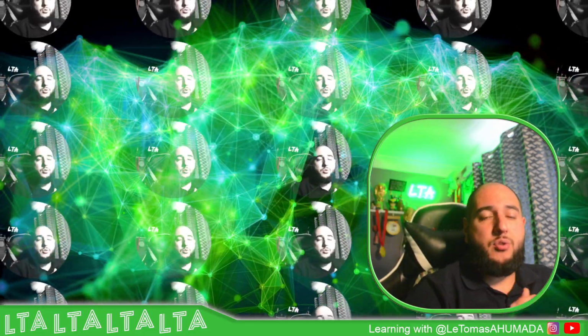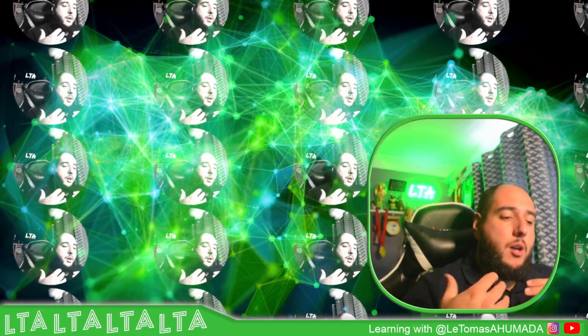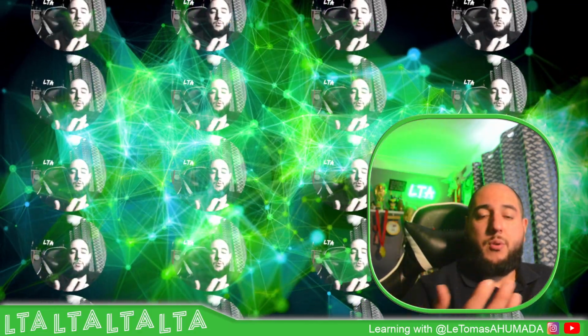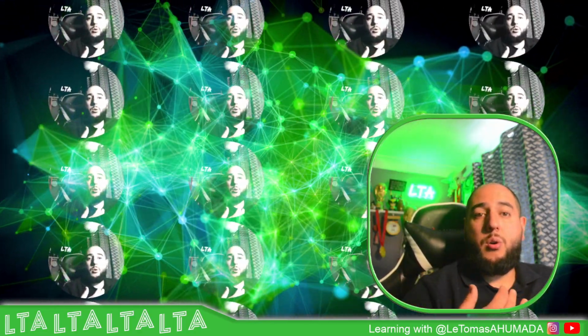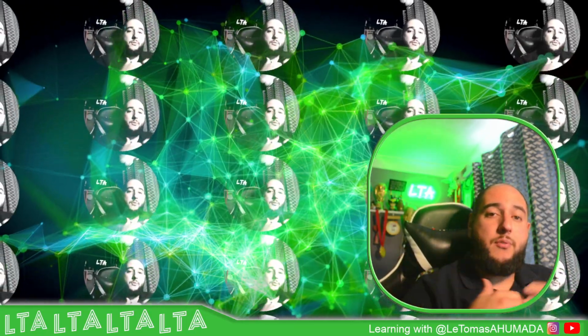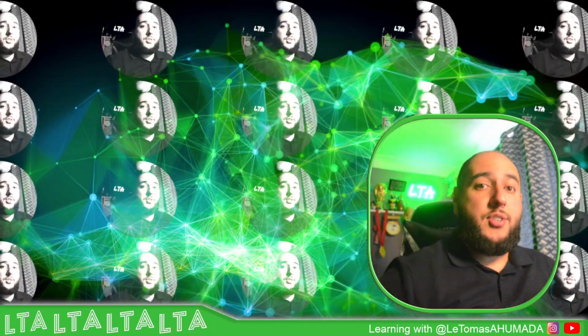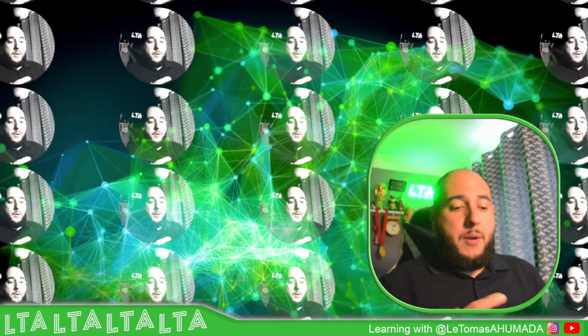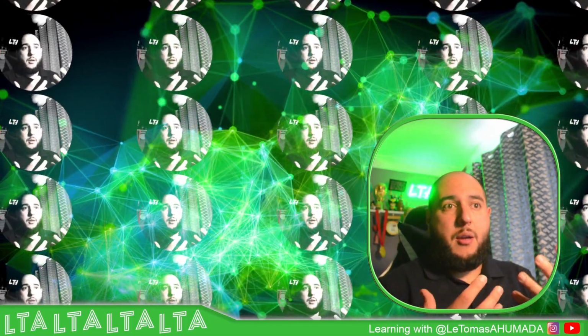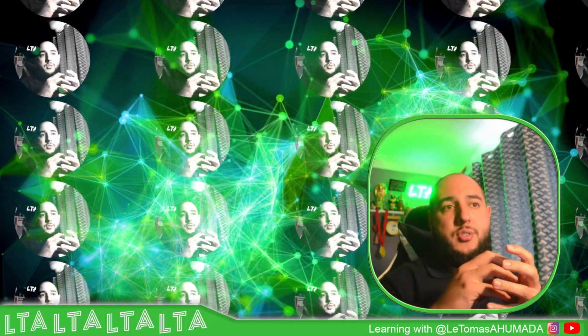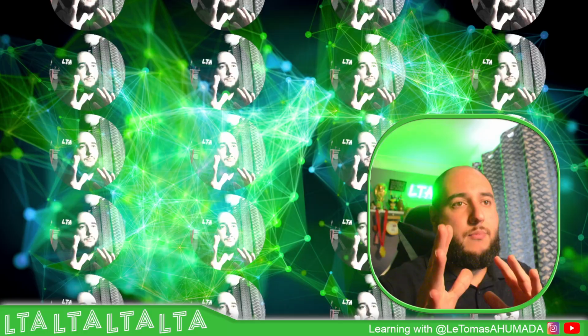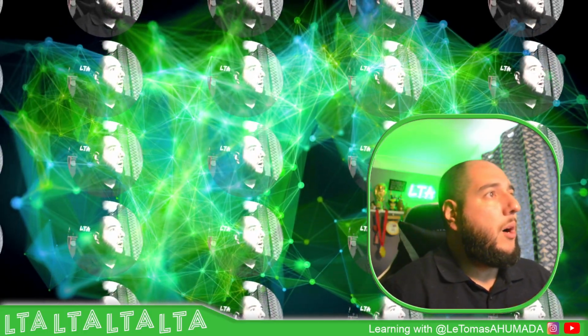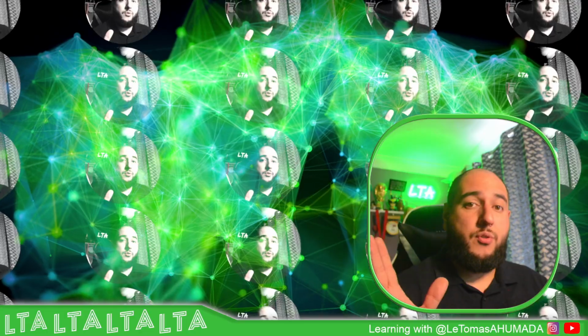Again, horizontal, vertical, and you just need to be sure if you want the CT version or the CTB version, so you can use the voltage part. And that is a little bit different compared with the TeSys T. The TeSys T has the CT already embedded in the control part, but in order to have the voltage, you have an independent model and just need to put it together. Here it is similar. So this is for the sensor modules for the TeSys Tera.